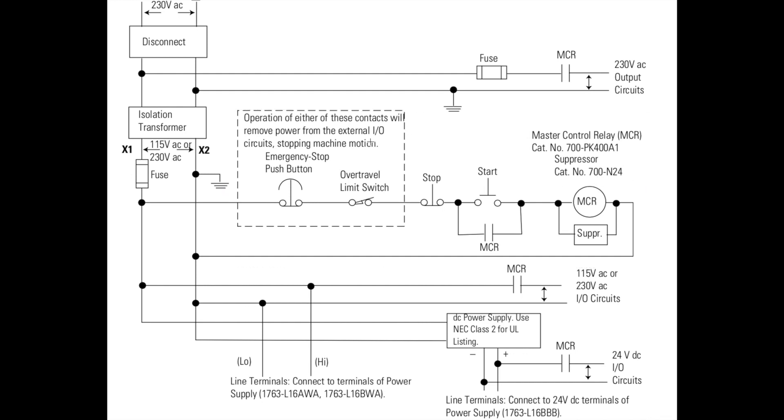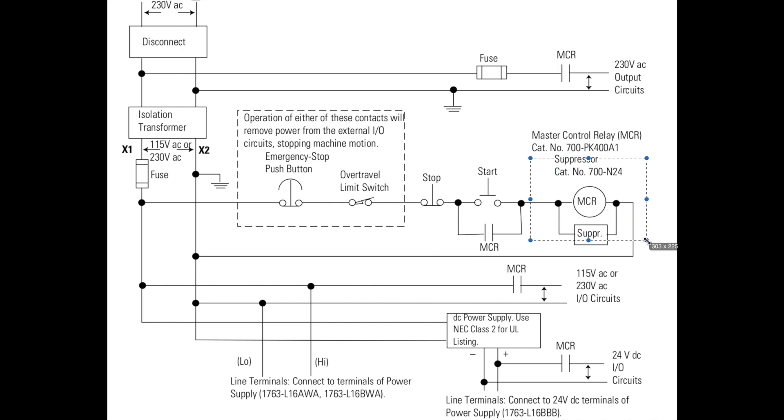Another thing that is important - this is a 120-volt system. You can see it's coming off of this leg and this leg, so it should be 120 volts. This coil probably has a 120-volt coil. We're not going to do it that way. We're going to put a transformer in between here. The reason is I already have a bunch of 24-volt relays, and I'm not going to buy 120-volt just to do this because it will get lost and mixed up.